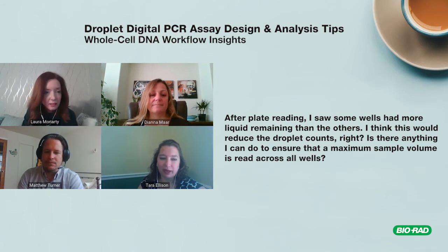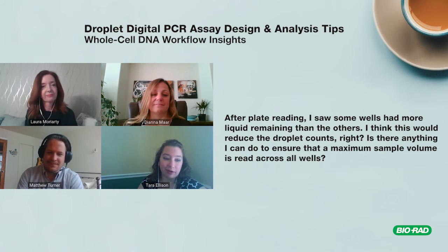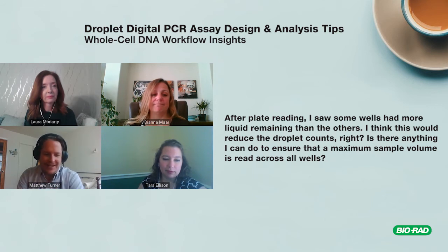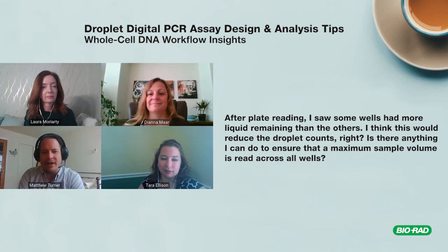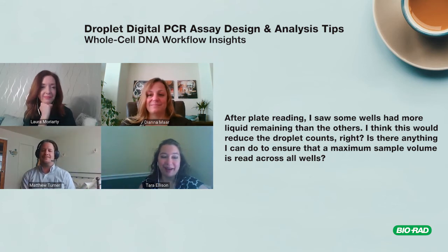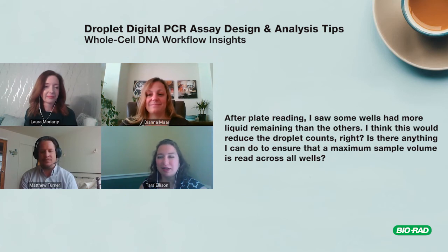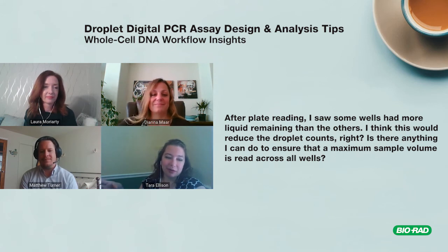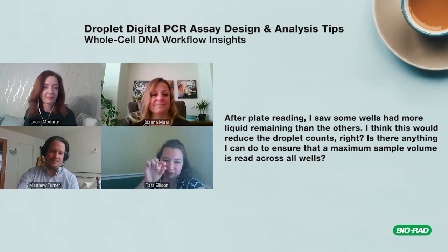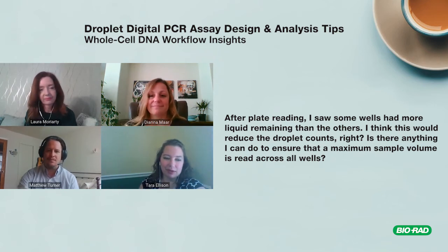Tara recommended doing a side check of the plate before putting it in the reader to see if any wells start off higher than others. Matt also noted: make sure you're using a ddPCR plate, since other plates may have slightly different depths. Tara confirmed with a field story — she once found a lab getting very few droplets because they were using unskirted plates that sat too low, so the reader was only picking up a tiny portion of the reaction.